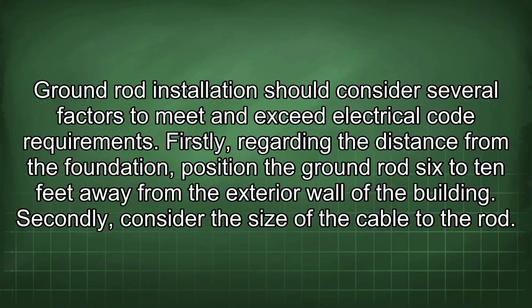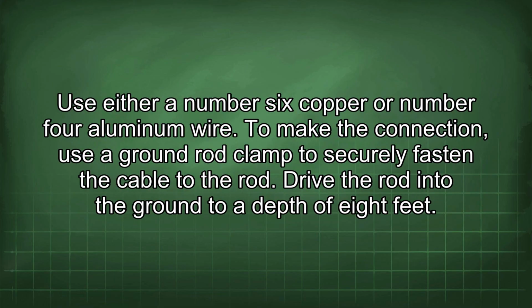Ground rod installation should consider several factors to meet and exceed electrical code requirements. Firstly, regarding the distance from the foundation, position the ground rod 6 to 10 feet away from the exterior wall of the building. Secondly, consider the size of the cable to the rod. Use either number 6 copper or number 4 aluminum wire.